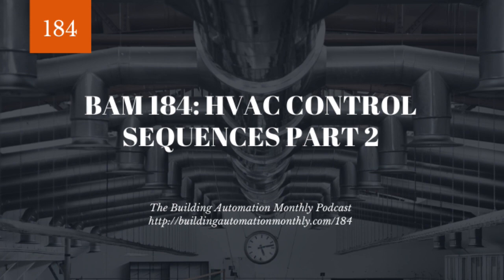But those are two ways, right, of using temperature as well as enthalpy comparisons in order to drive outdoor air damper enablement and to drive it to control. Now, outdoor air dampers will also drive to control the discharge air temp, kind of like the cooling coil sequence. So you have a DX coil sequence. You'll drive the damper open and shut to control the temperature. Typically zone temp, sometimes discharge air, sometimes mixed air temp. It depends on the sequence.